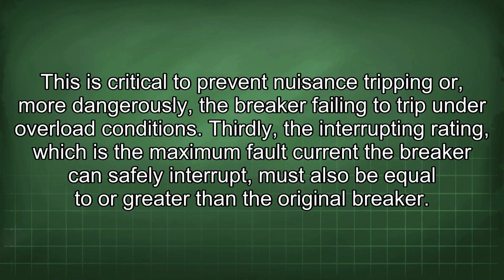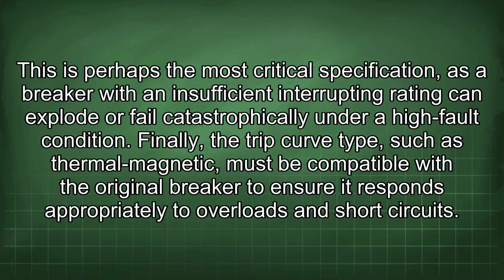Thirdly, the interrupting rating, which is the maximum fault current the breaker can safely interrupt, must also be equal to or greater than the original breaker. This is perhaps the most critical specification, as a breaker with an insufficient interrupting rating can explode or fail catastrophically under a high fault condition. Finally, the trip curve type, such as thermal magnetic, must be compatible with the original breaker to ensure it responds appropriately to overloads and short circuits.